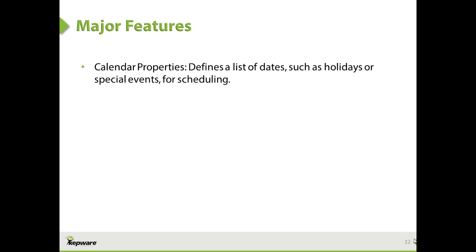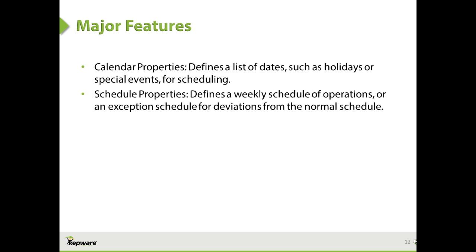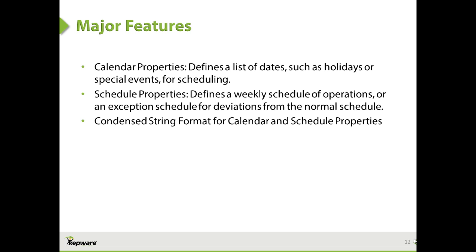The BACnet IP driver for KEPServerEX now supports reading and writing of these new properties for the calendar and schedule objects. Features include calendar properties, which define a read-write date list for holidays or special events; schedule properties, which define a weekly schedule of operations or an exception schedule; condensed string format for these tag items, which is how they're displayed; and automatic tag generation for these properties from the controller. Let's move on to a demo of these new features.